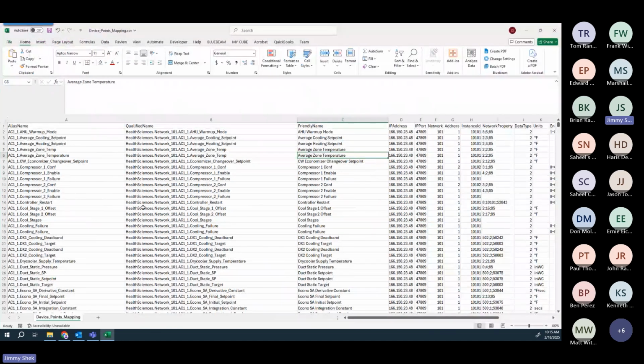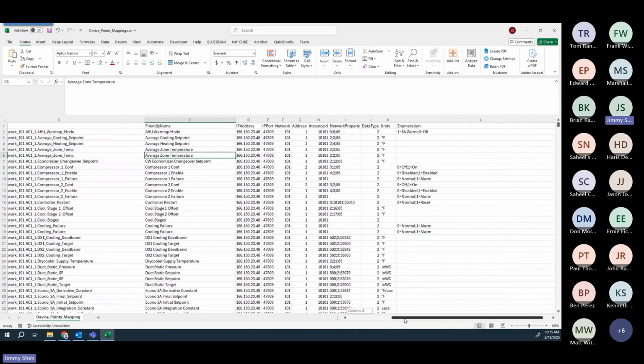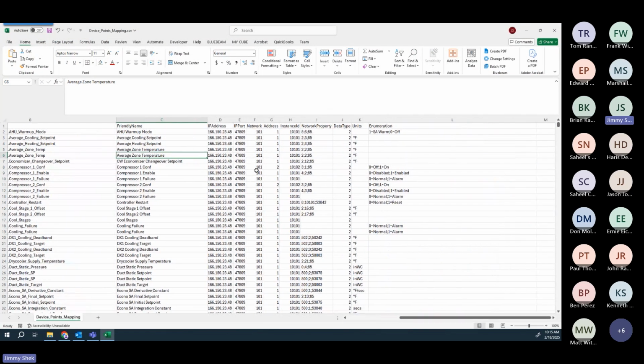This file here is basically just a parsed out listing of all the devices and points from the system, pulling out the important information, like the IP address and port, the MSTP network address, the controller address, instance ID, and ultimately the network property for each one of the points that we'll be interacting with. We also pull out things like the units and enumerations so that when you're writing these test cases, you can leverage that information, which makes it a lot more readable.